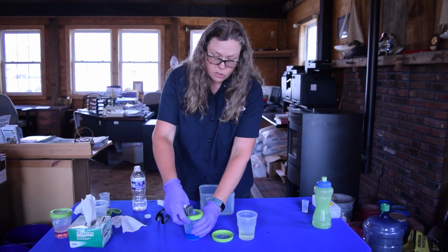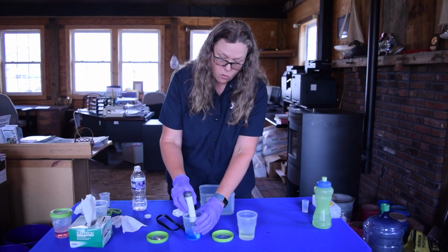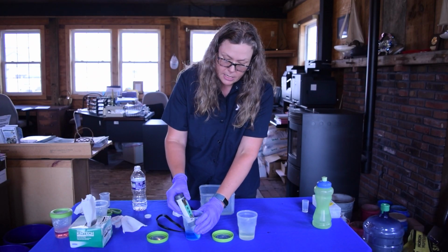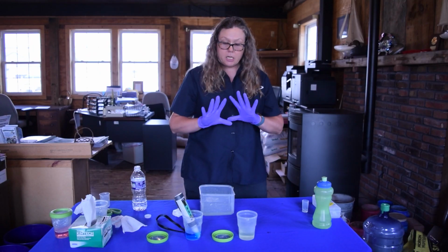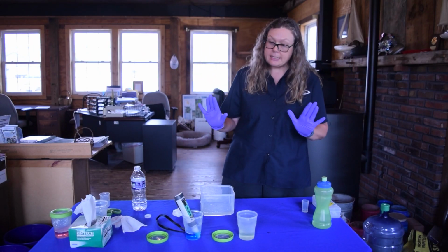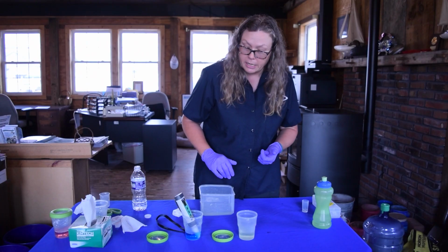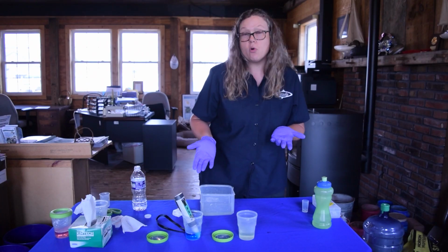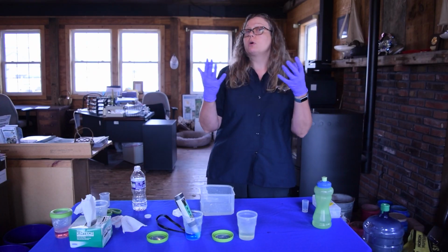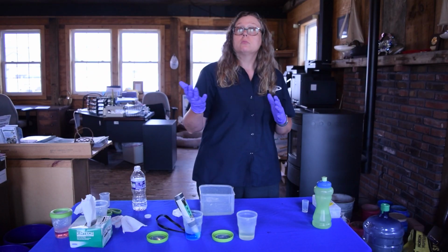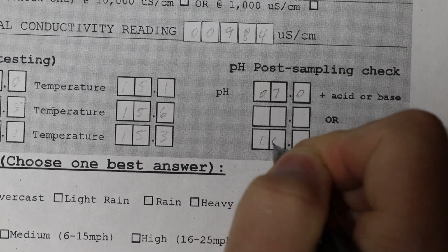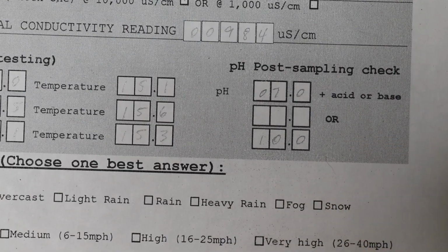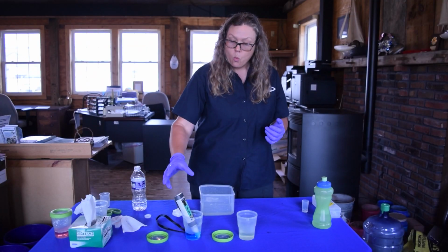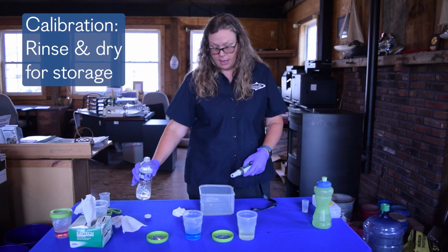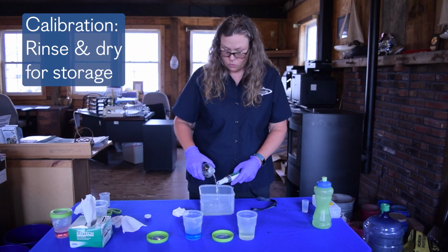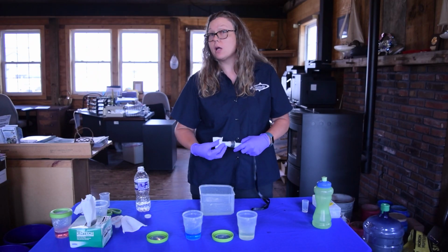And we're going to need to do the same thing with our acidic or basic. And in this case, it's our basic. So again, hands-free. We're not pressing any buttons. We are only taking a reading. And look at this, 10.01. So we would record 10.0 in the post-sampling check column next to the basic solution. Once we've done that, we're going to do a last rinse, a last wipe until next time.